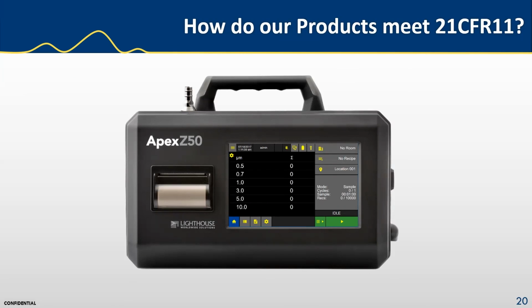A traceability matrix illustrates how the ApexZ was tested against the requirements of 21 CFR Part 11 internally, and there are also field verification documents like IQ and OQ documents available. I see more and more companies now ordering these validation packages, and it is important as vendors that we are able to fully verify the operation of the system to be compliant with 21 CFR Part 11. Now, when I say fully compliant, there are also requirements of the end user, and we'll get into them in a little more detail later.